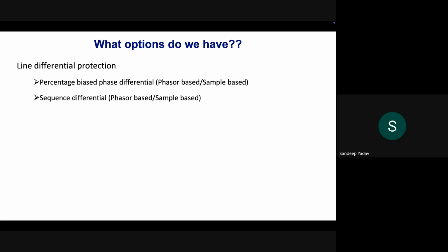Now it comes down to, if the distance relays are not the solution in case of RE generator ends, what options do we have? As we discussed in the beginning, line differential works good because it works on the principle of difference of the current. So even though the contribution from the RE generator end is not much, because the contribution from the grid side is large, the differential current will be high and the protection will always operate. So, and then there are different nuances, what kind of differential algorithm we should use. Should it be percentage biased?